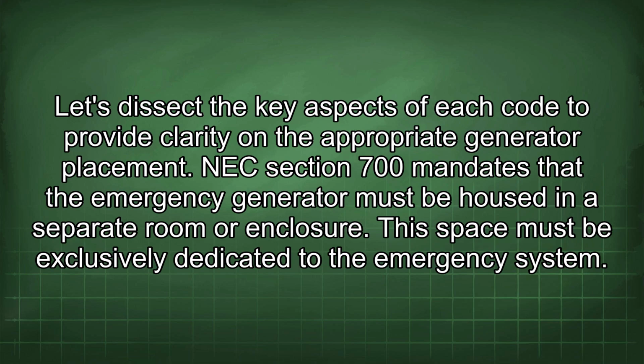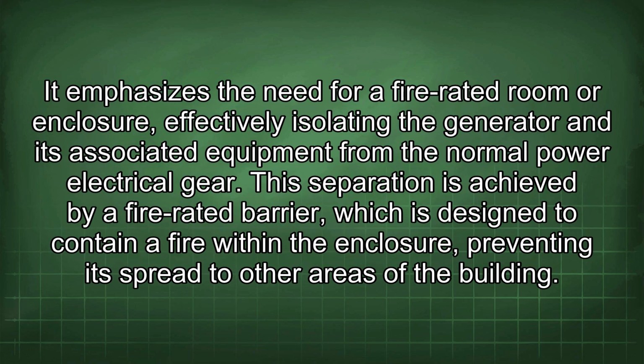NEC Section 700 mandates that the emergency generator must be housed in a separate room or enclosure. This space must be exclusively dedicated to the emergency system. It emphasizes the need for a fire-rated room or enclosure, effectively isolating the generator and its associated equipment from the normal power electrical gear. This separation is achieved by a fire-rated barrier, which is designed to contain a fire within the enclosure, preventing its spread to other areas of the building.